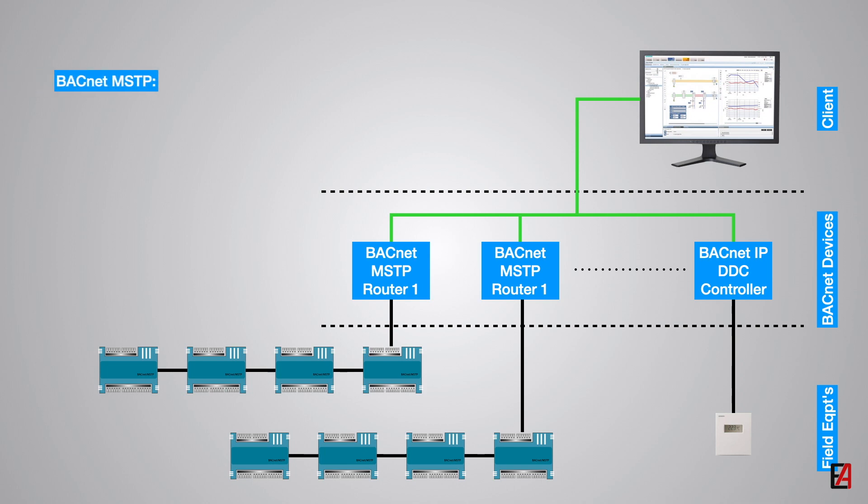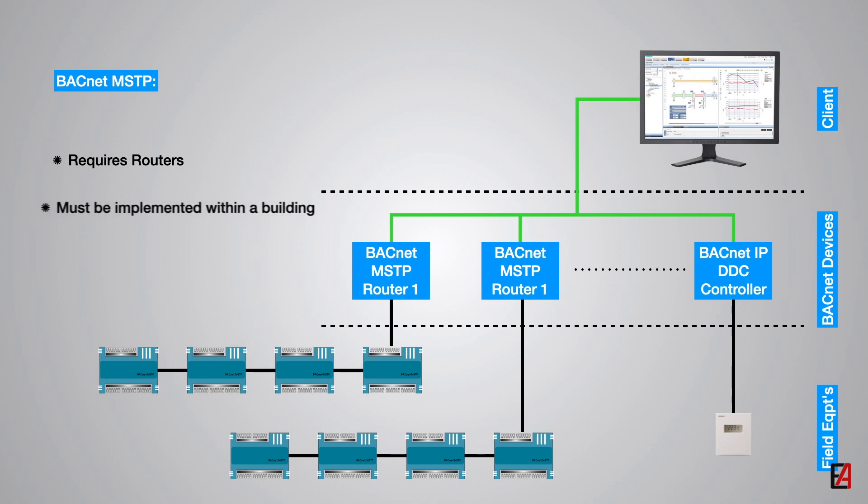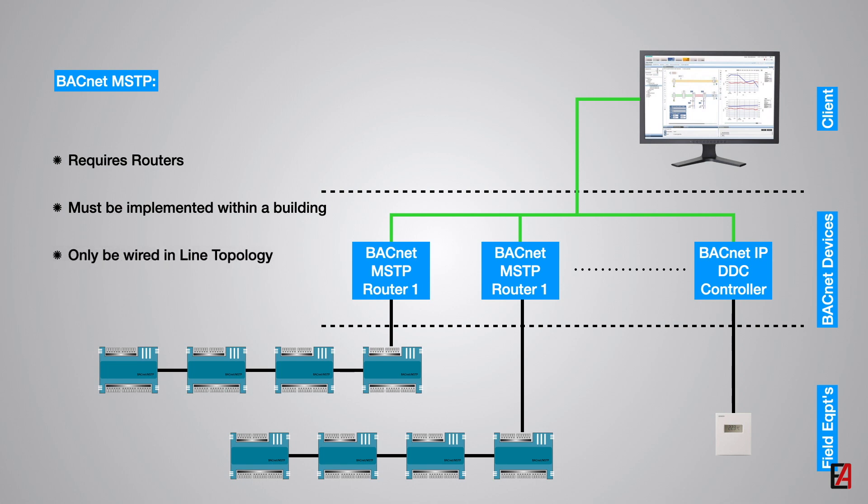Some important points to remember while selecting a BACnet MSTP system are: BACnet MSTP system always requires routers on the network. BACnet MSTP network supports lengths up to 1200 meters. However, it should be noted that the MSTP network must be implemented only within the building. If you have multiple buildings, use separate MSTP networks with routers on each building. Wiring must be done only in line topology following the daisy chain format.